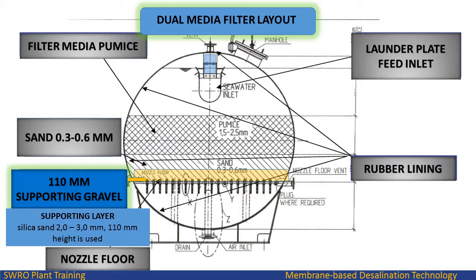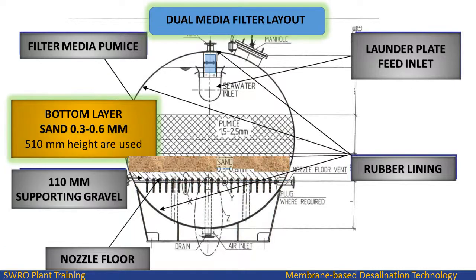Supporting layer: filled with silica sand 2.0 to 3.0 millimetres, with a height of 110 millimetres. It is used to support the sand media layer. Bottom layer: filled with silica sand 0.3 to 0.6 millimetres, with a height of 510 millimetres.